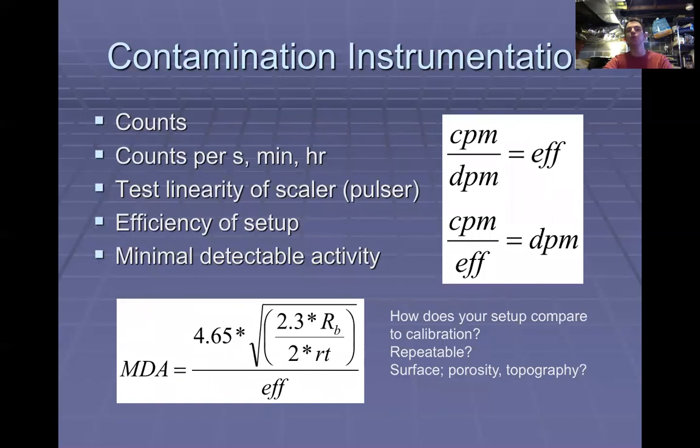There's this idea of minimum detectable activity. You want to know the lowest level of what your instrument is capable of seeing, because if you have a meter that has a background of 30, 40 CPM, so it's okay, and then you measure a spot and you get 60 CPM, is that real? It's above your background, but if you've ever turned on a GM, you'll see the scale just kind of fluctuating. It never stays still. So it's very difficult to know what's real versus what's not real.